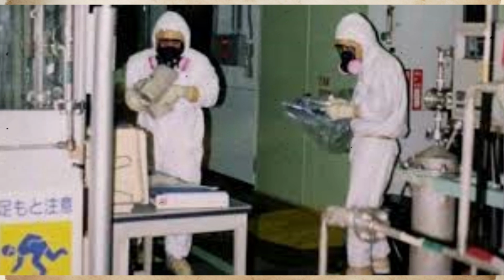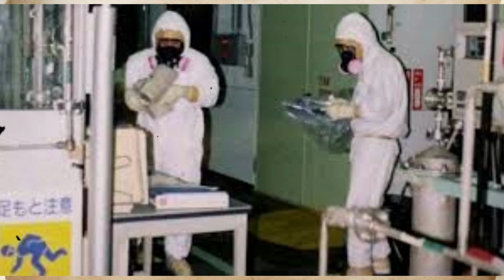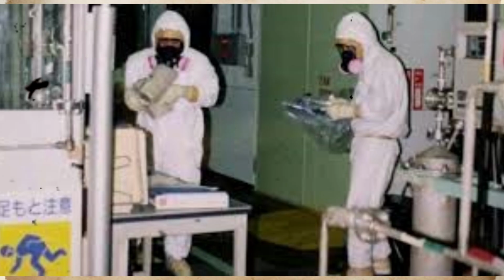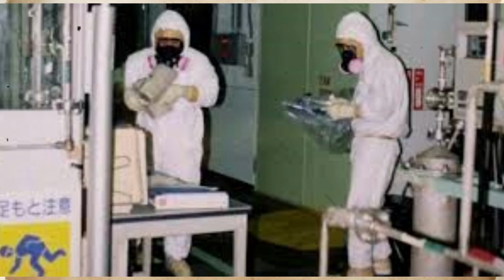Reactor vessel examinations revealed extensive fuel damage with significant fuel debris relocation. Containment inspections found evidence of corium formation and migration outside the original core configuration. Suppression pool examinations revealed structural damage from high-temperature conditions and hydrogen combustion effects. This post-accident evidence validated theoretical understanding of severe accident progression, while revealing that actual conditions had been even more severe than real-time assessments suggested. The core damage at Fukushima Daiichi was not merely fuel cladding failure or partial fuel melting, but extensive fuel relocation and corium formation that challenged fundamental assumptions about core geometry and coolability.